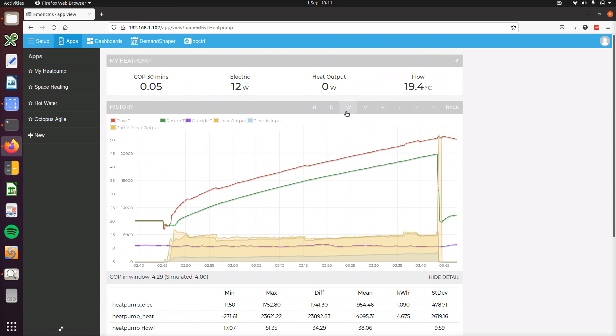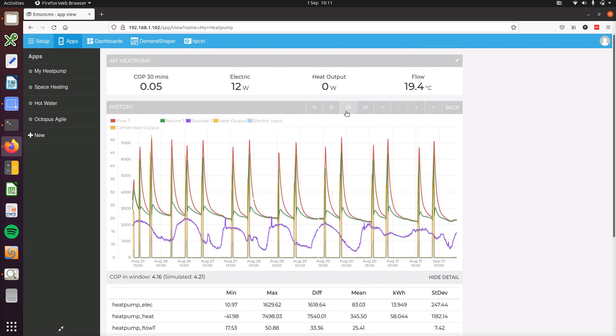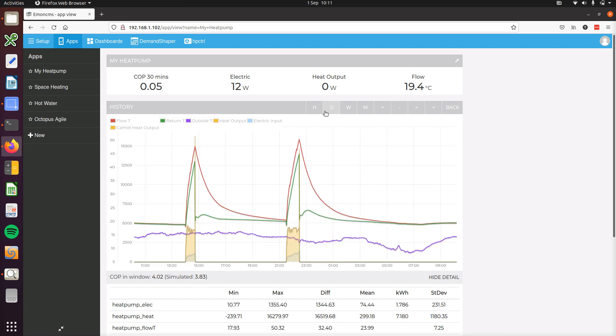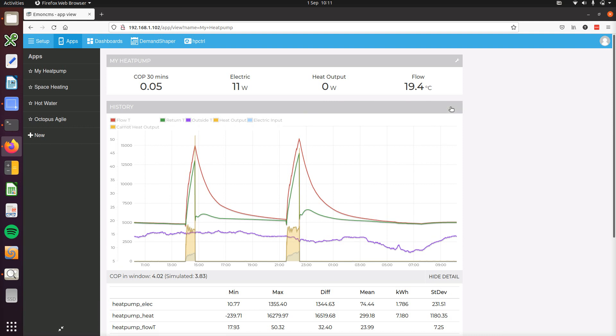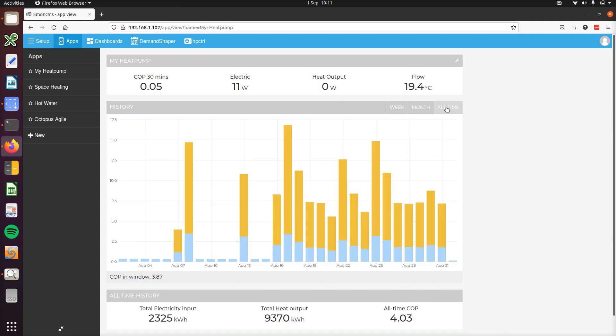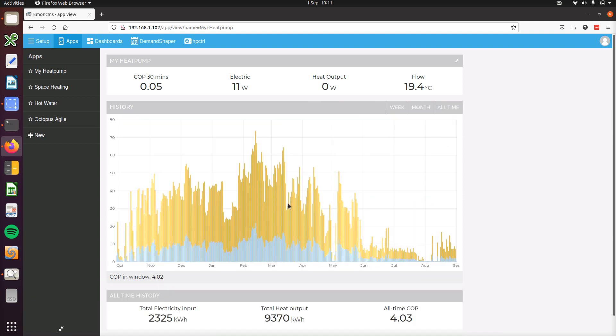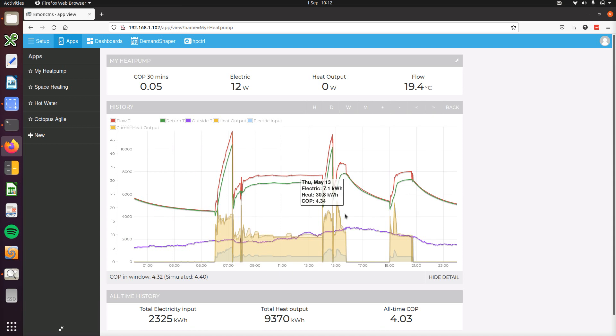So if I look over the last day, we've got a simulated COP of 3.8 and actual COP of 4. Now I'll go to a period which has more space heating maybe here in May, simulated COP 4.4 and actual measured COP 4.3.